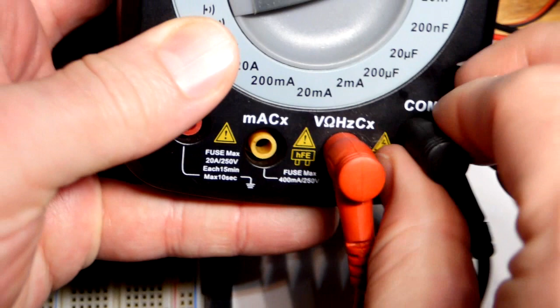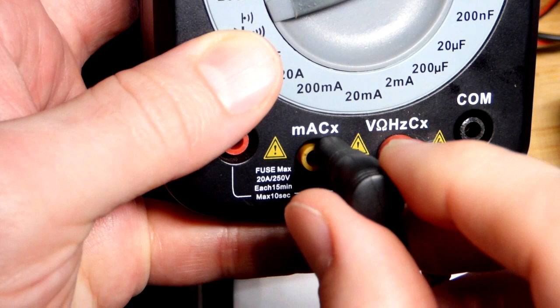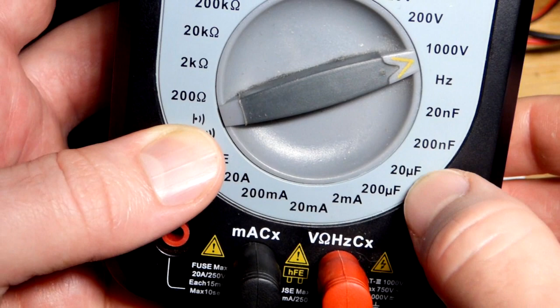So now in this video, we're going to measure capacitance. One of the first things we need to do for this meter is put the black probe where you see capacitance, since some meters don't require you to move anything. This one isn't black because when you measure milliamps of current, you leave the black probe there and move the red probe over. We are going to measure more than 20 microfarad of capacitance, although the first two measurements will be less.